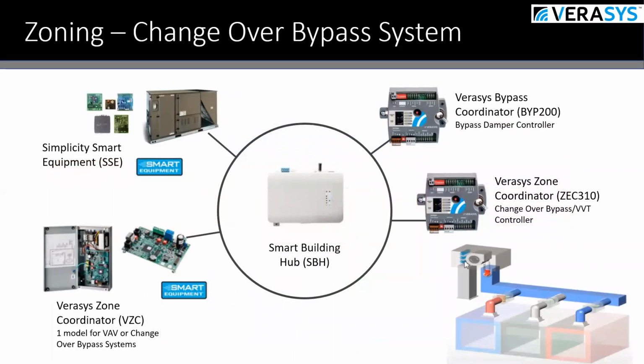Now, this is just a little overview on zoning for a changeover bypass system. Zoning in Verasys is very popular. In this example, zoning may consist of a bypass controller that you may or may not need, but each zone coordinator on a changeover bypass system can manage up to 32 zones.